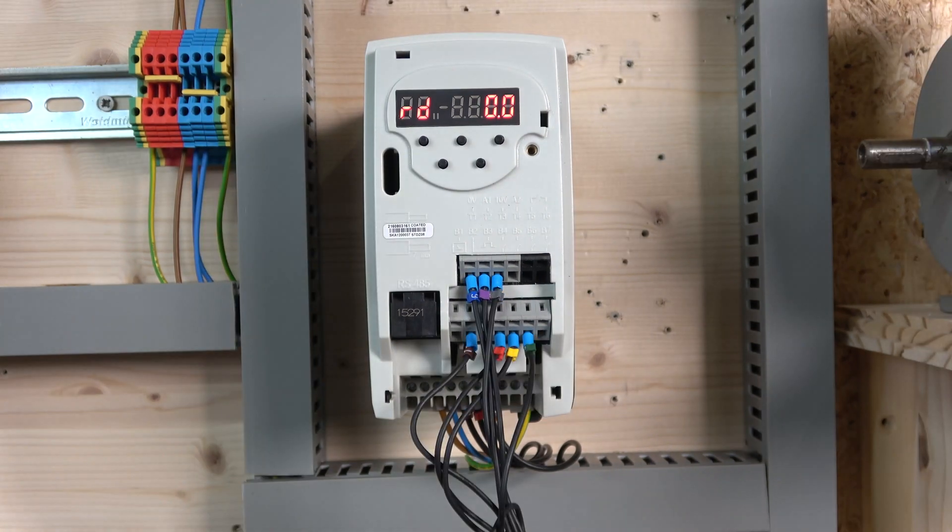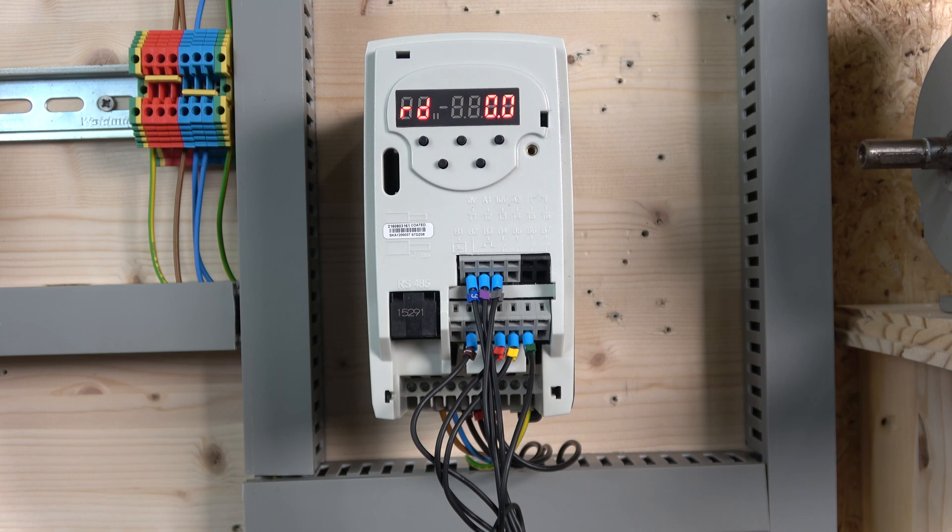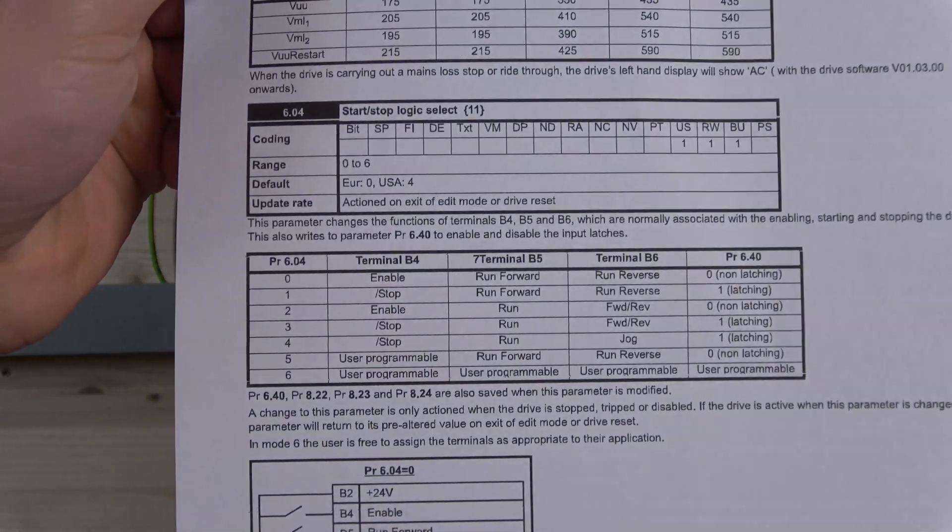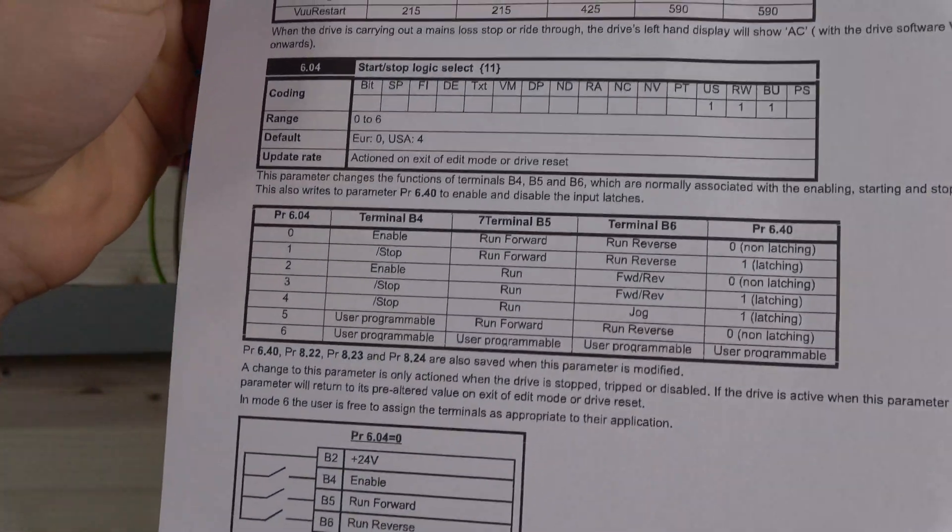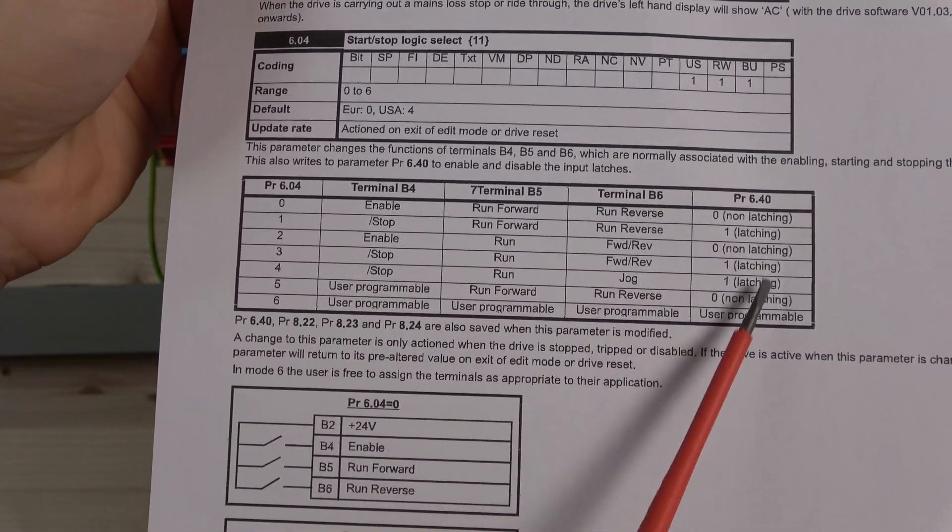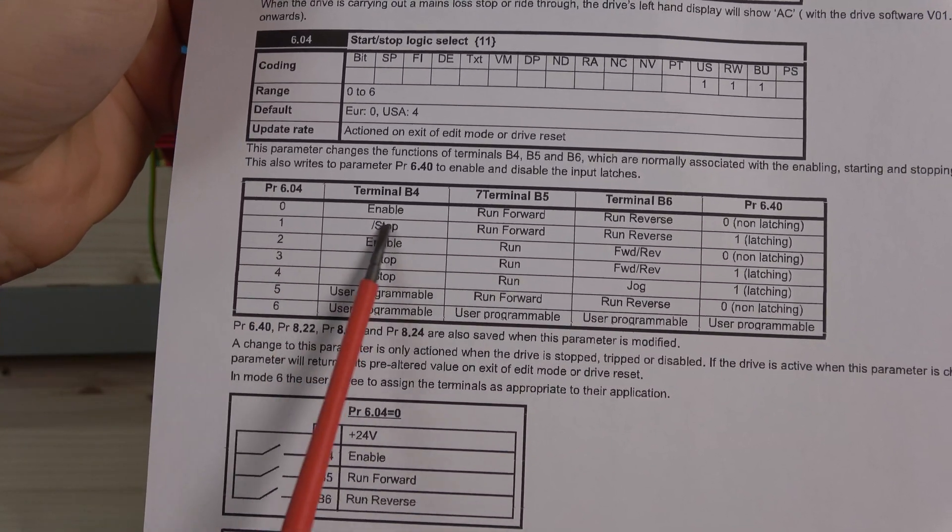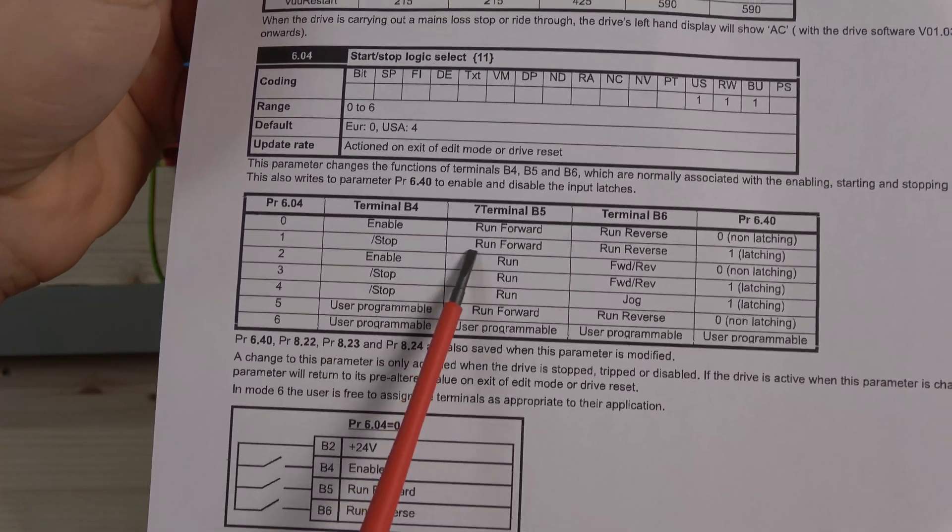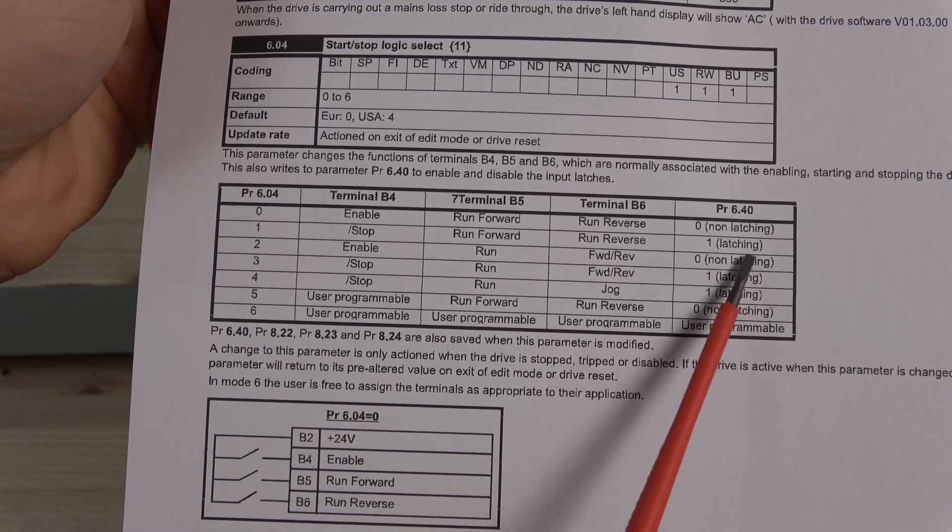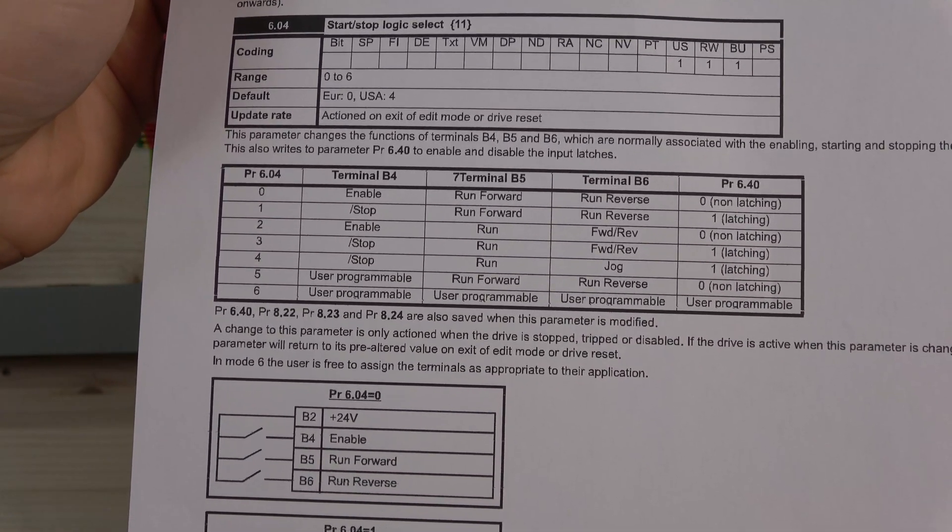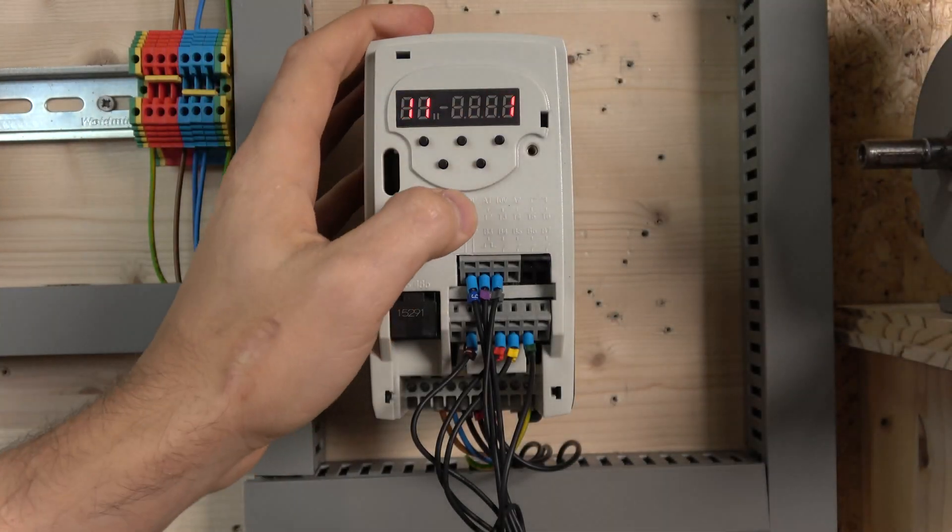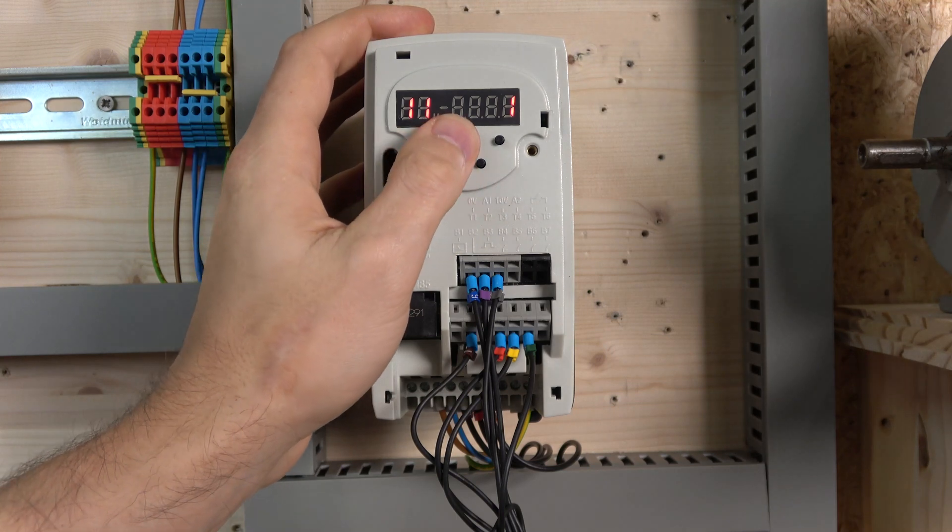As for the 3-wire control, there's only one parameter that we need to change for this to work. We're going to keep Parameter 5 as it is, and we're going to change Parameter 11 to start-stop logic selection. If you look at it here, Parameter 6.04 in the advanced menu sort of tells you what states you can have. We're going to be working with this one here. Terminal 4 is going to be our stop, run forwards and run reverse. You can see down here it shows latching. So that's what we're trying to achieve. All you need to do is go into Parameter 11 and change that to 1.